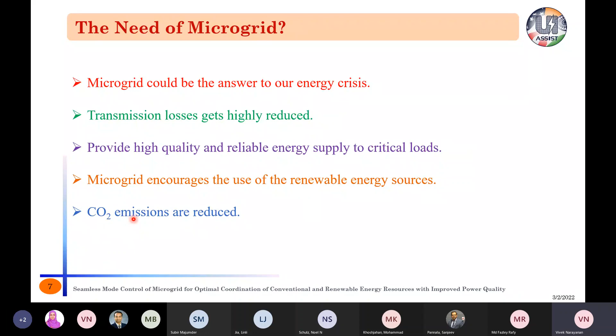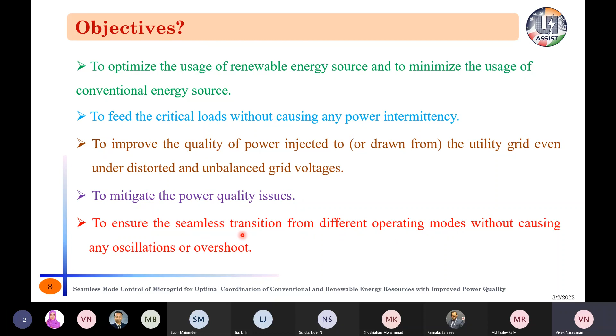And the main objective is to optimize the usage of renewable energy source and to minimize the usage of conventional diesel generator source to feed the critical loads without causing any power intermittency, and to improve the quality of power injected to the utility grid or drawn from the utility grid depending upon the generation as well as demand under distorted as well as unbalanced grid voltages, and to mitigate the power quality issues such as compensation of harmonics, compensation of reactive power, and balancing of utility grid or DG set currents even though it is feeding unbalanced loads, and to ensure the seamless transition from different operating modes without causing any oscillation or overshoot.